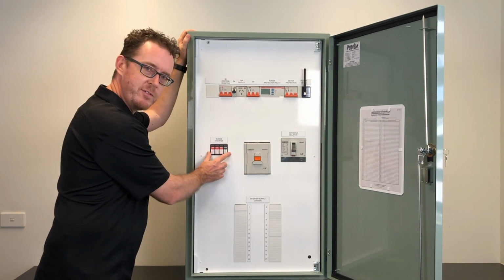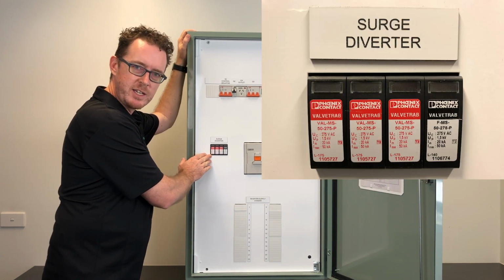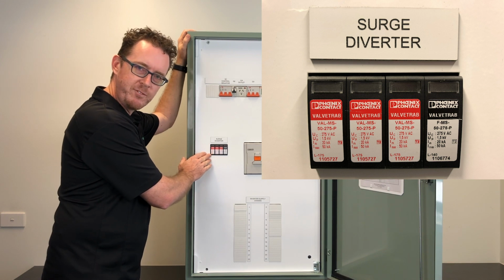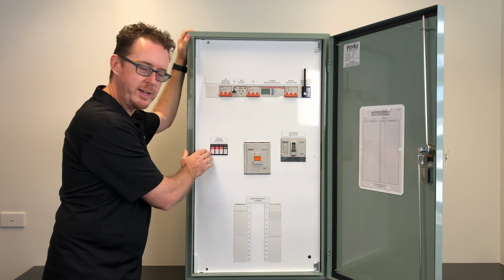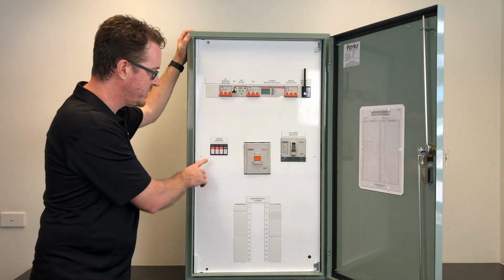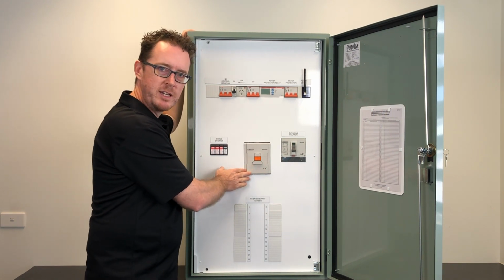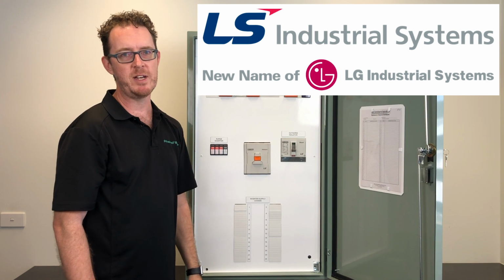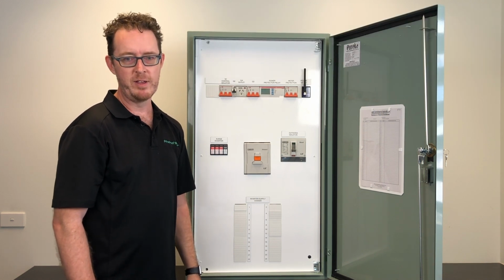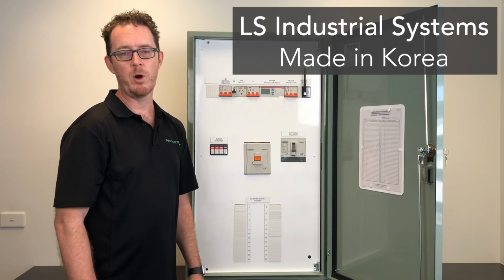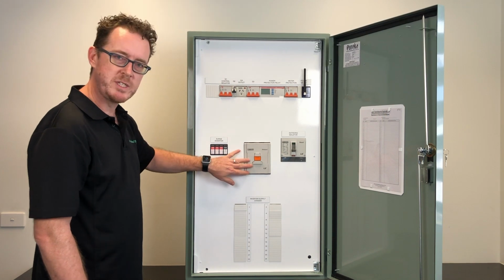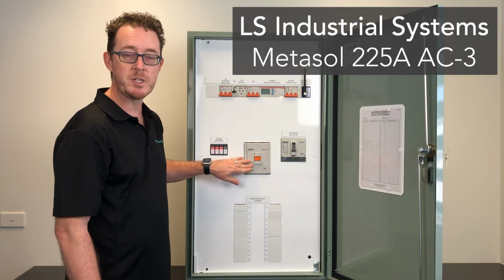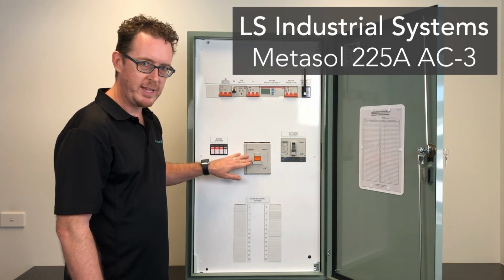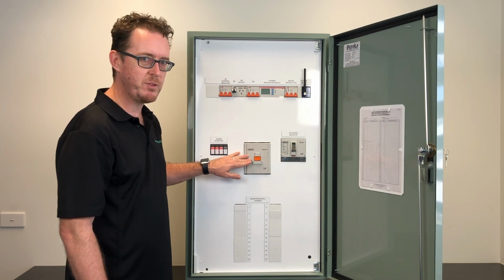And then you can see here we have an optional accessory, in this case a surge diverter. So this won't be a standard inclusion, but it will be available as an accessory, and there'll be instructions on how to wire it in. And of course there's already the location in the escutcheon built in for this. In the center we have the contactor. So we're using high quality LS industrial systems switchgear here. LS was founded in the 70s. It was originally part of the Lucky Gold Star group, which went on to be LG. They were spun off in 2003, and they've been their own standalone business since the early 2000s. This particular contactor is rated at 225 amps AC3. So that means that we absolutely have the 100 kilowatt sized installations covered without any problems at all.